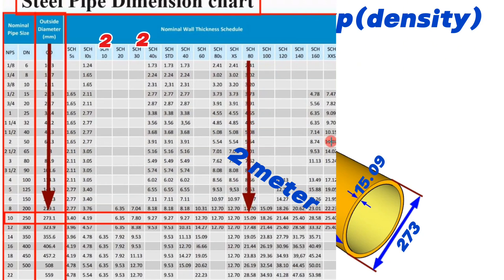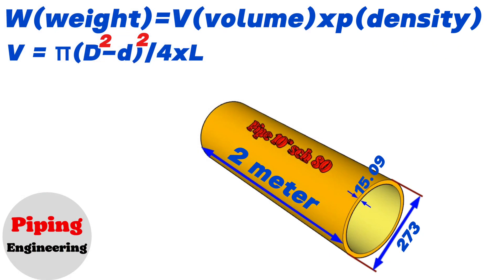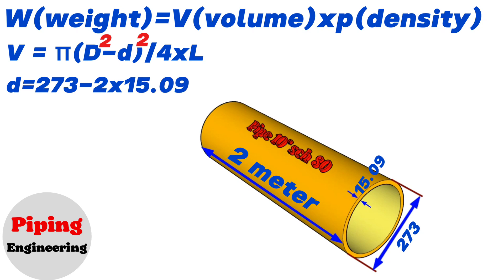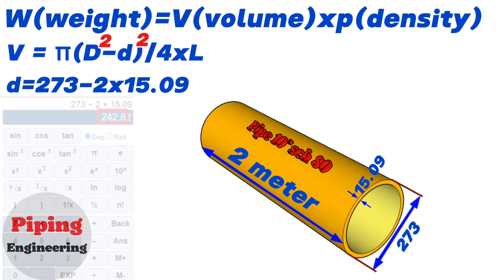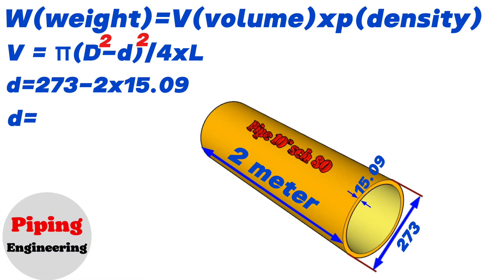Now we can calculate the inside diameter of this 10 inch pipe. The inside diameter equals the outside diameter 273 minus 2 times the wall thickness 15.09. Using the calculator, we find that 273 minus 2 times 15.09 equals approximately 243. So we calculated and found that the inside diameter of the 10 inch schedule 80 pipe is 243 millimeters.